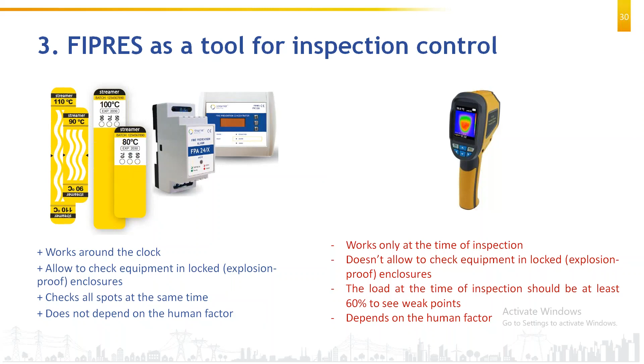Loads are varying in different ranges, and sometimes loads are not there also. It does not depend on the human factor. It does 24/7 monitoring automatically, whereas thermography depends on the human factor. Then the scope of application: wherever there is a switchgear or electrical panel, but especially where there is explosion-protected electrical equipment, because the technical staff cannot open the explosion-proof housing during operation of the equipment and cannot check the equipment by thermal imager.